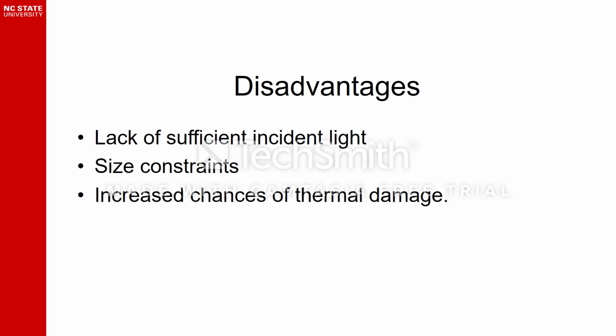One of the major disadvantages of subretinal implants is the lack of sufficient light for photodiodes to produce electric current. Because of this, implants use an external power source to amplify the incident light. Since the subretinal space is quite small, it imposes size restrictions on the device. Also, the close proximity between the implant and the retina increases the chances of thermal damage to the retina. Since these devices depend on the inner and middle layers of the retina, they are not effective for retinal diseases extending beyond the photoreceptor layer.